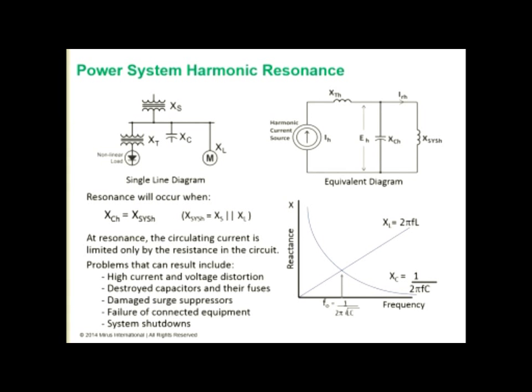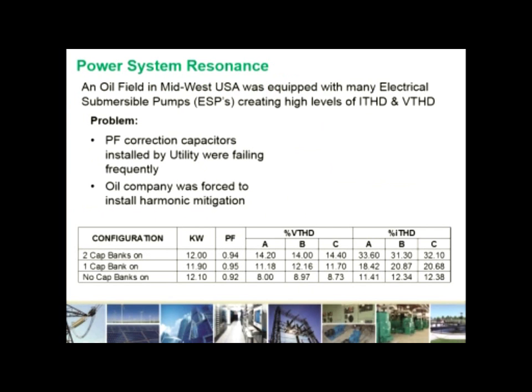These high levels of current and voltage distortion can destroy the capacitors and the fuses protecting those capacitors. Can damage surge suppression equipment. It can cause failure of connected equipment on the bus because your bus voltage gets badly distorted, and thereby can result in system shutdowns. So resonance is definitely a condition that we want to avoid. And I'd just like to provide an example of where a power system resonance occurred. And the utility and the utility's customer weren't aware of it until after it had caused a lot of problems on their system.